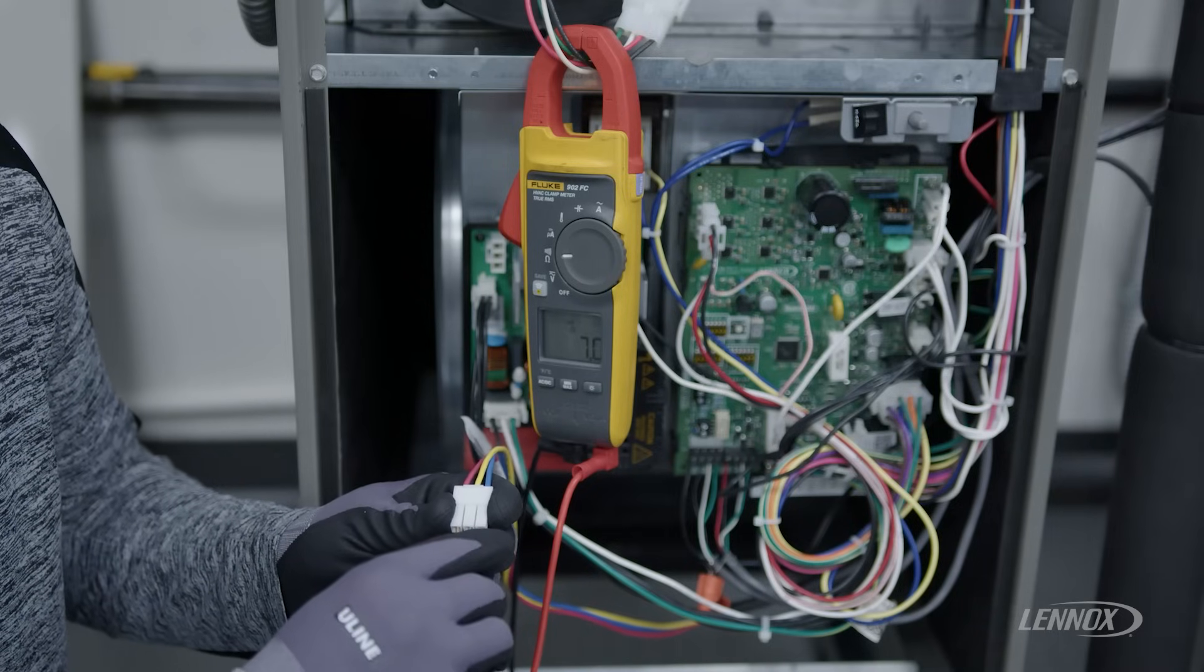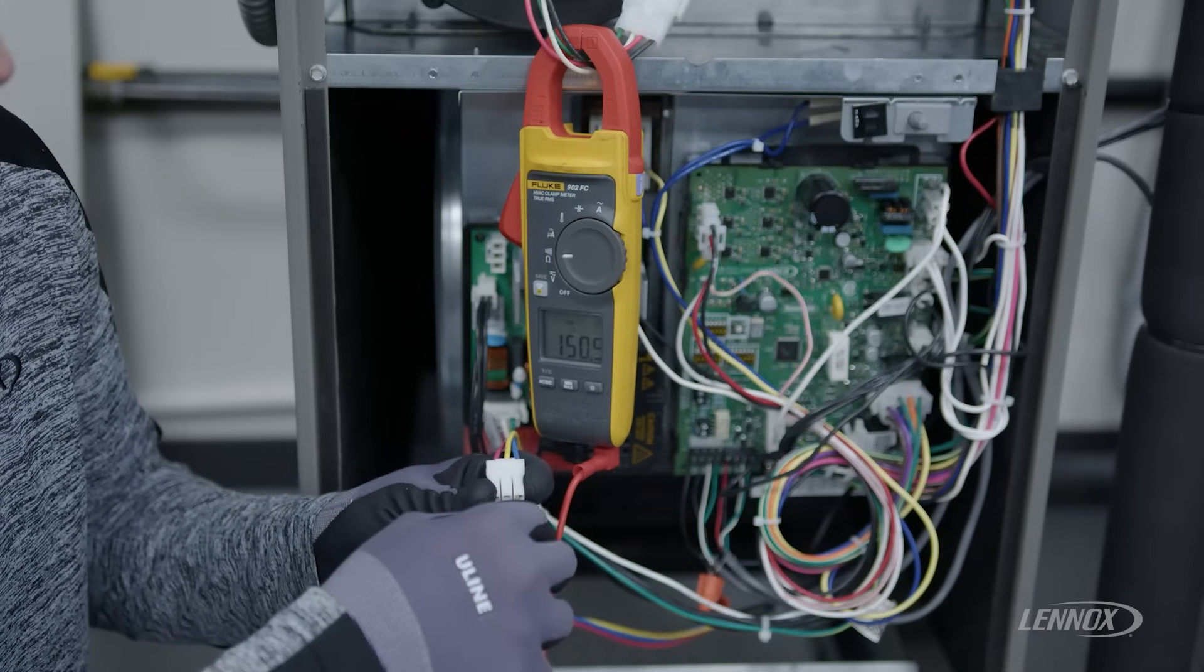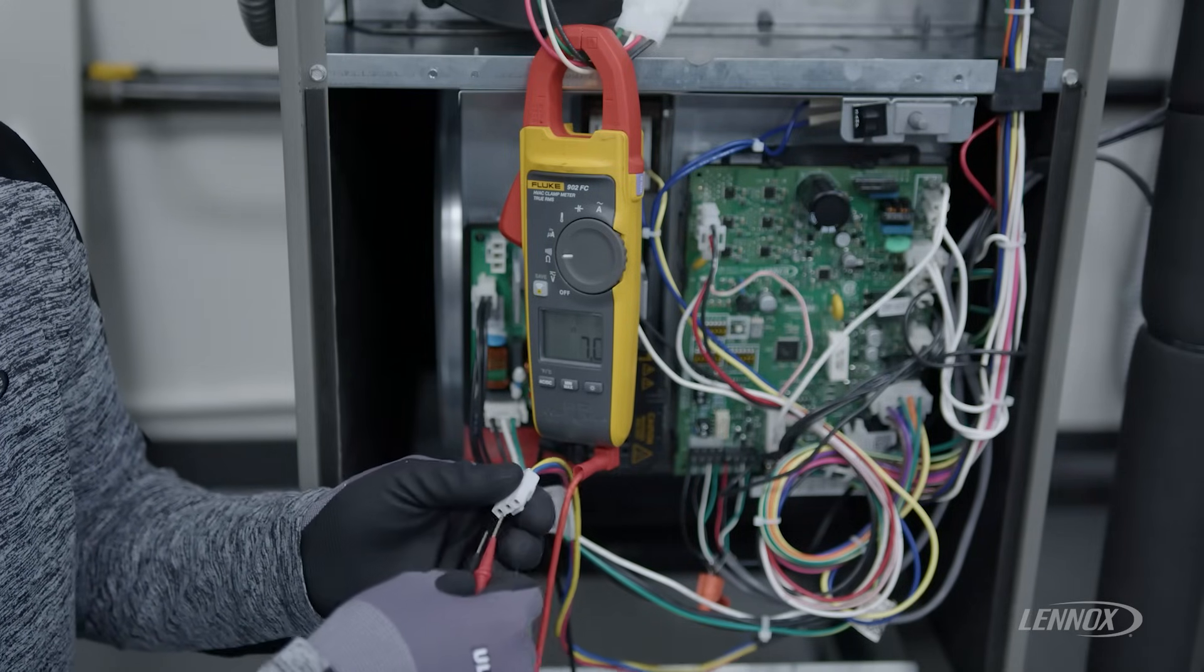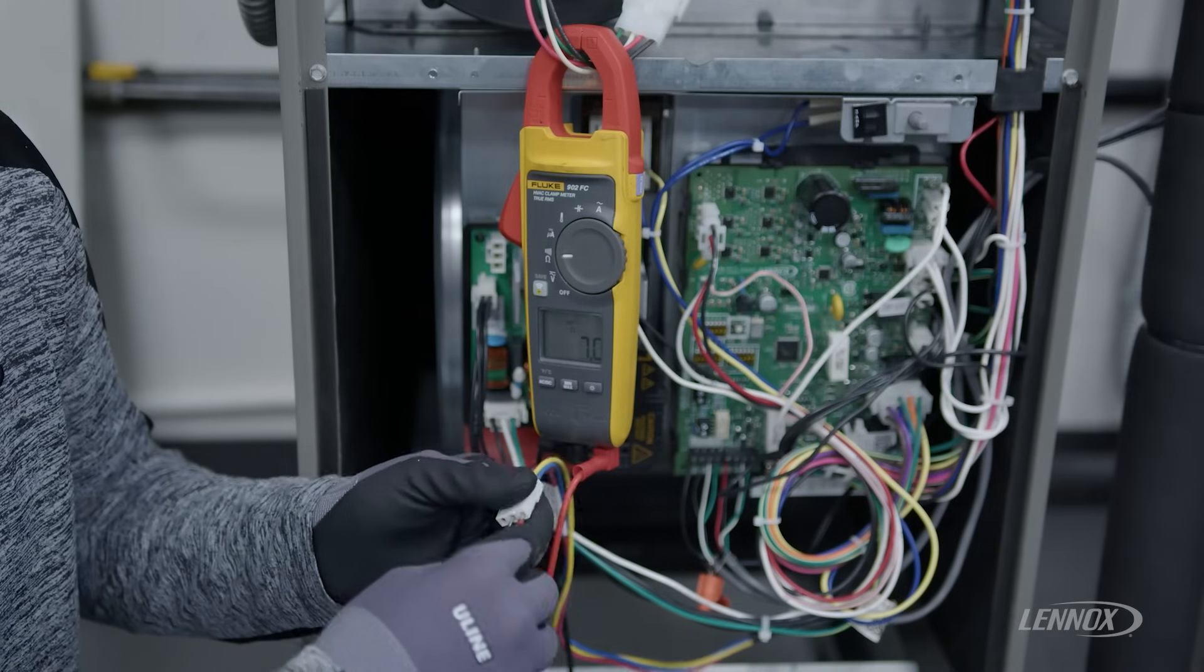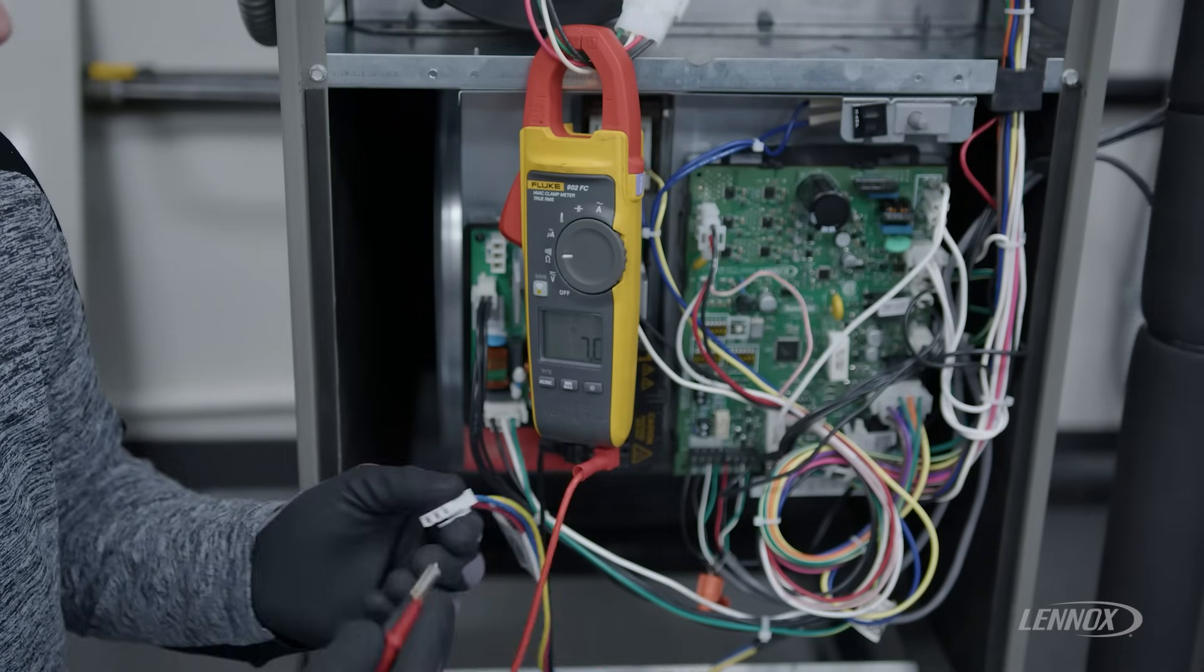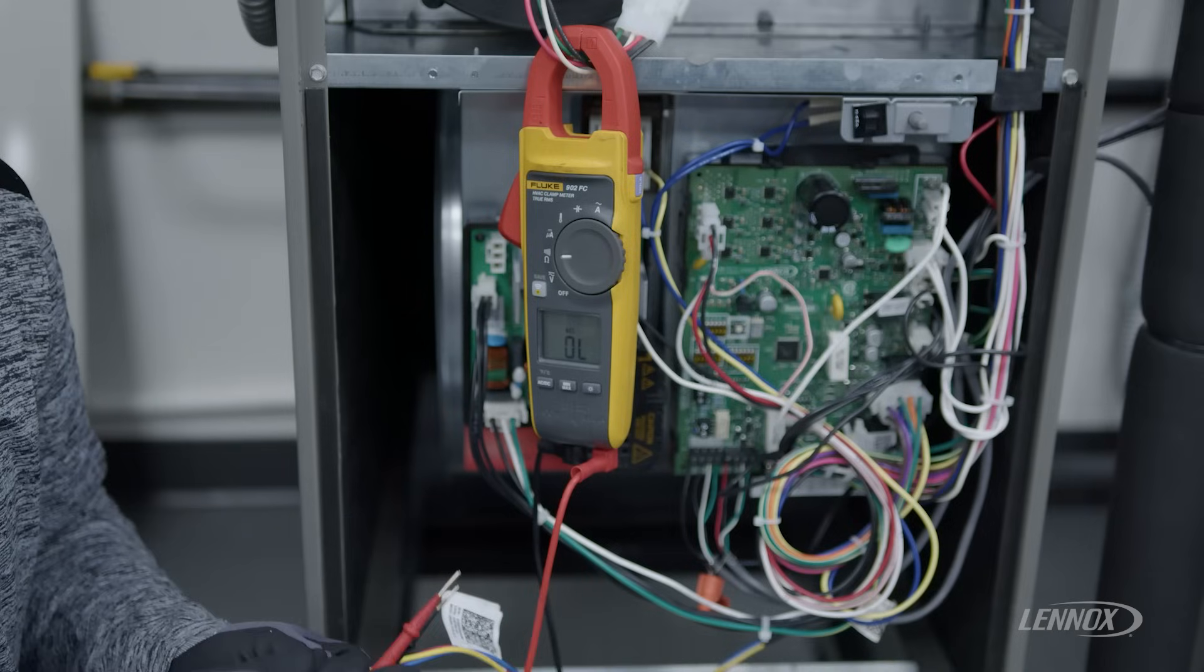Red to yellow is 7.1, red to blue is 7.0, and blue to yellow is 7.0, indicating that our windings are all in line with one another and that this motor is in good shape.